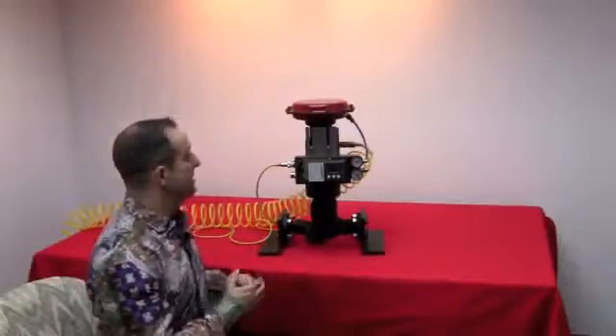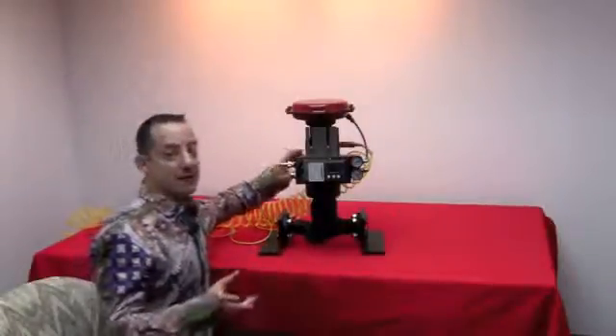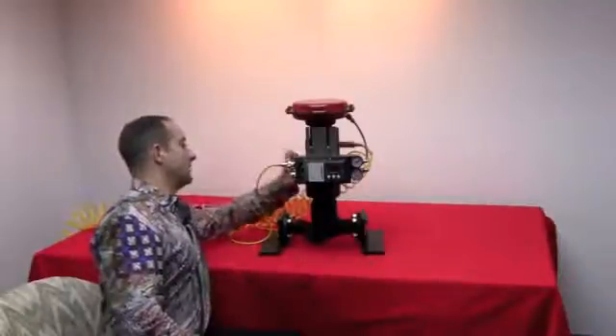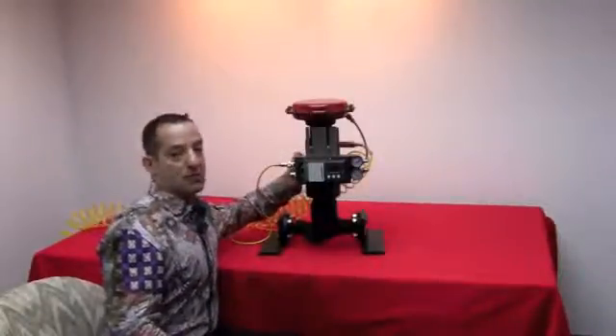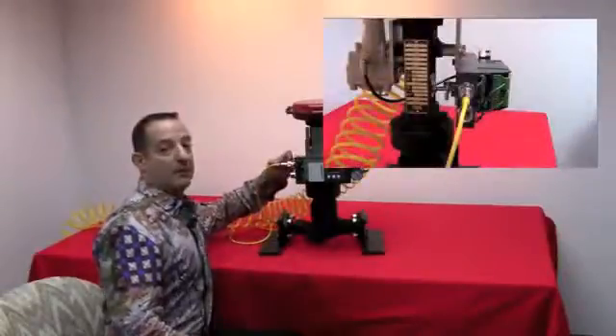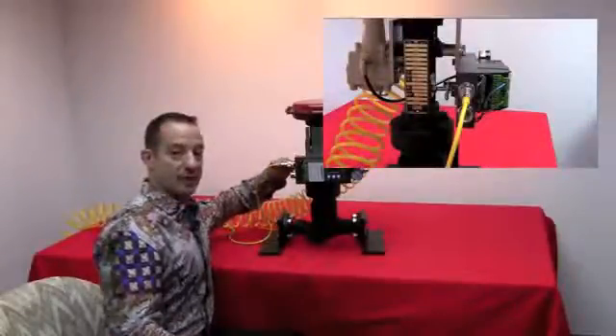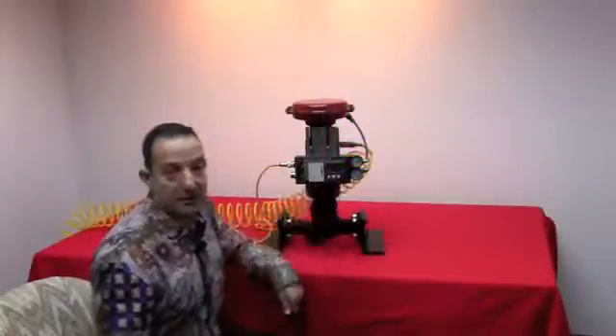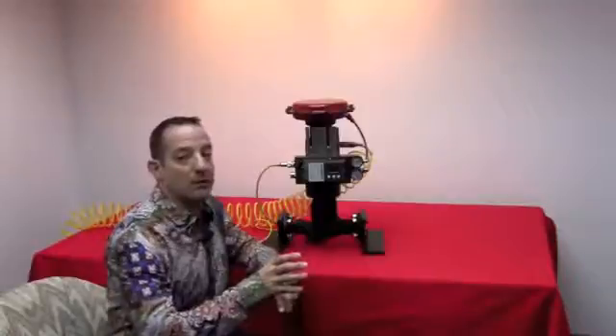Proper mounting involves following the instructions in the mounting kit and almost always ensuring that the valve is at mid-stroke. At the same time, the feedback arm is in the horizontal position and at the same time, the position display on the front of the unit reads somewhere around 50%.